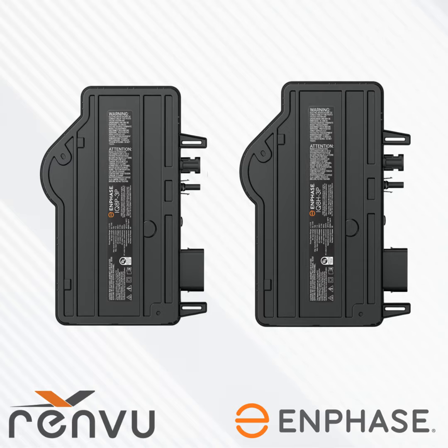So let's look at the specs a little more with a little more focus. We offer two different inverters, the IQ8P and the IQ8H, and the specifications are as follows. The 8P has a max output of 480 VA, and the H has a max output of 384 VA. Most people would just say 480 or 384 watts, but since they're intelligent and reactive power sources that respond to site conditions, technically 480 or 384 VA is more accurate. Whenever I say VA, just think watt. Again, output is 208Y. If your site is a different voltage, add a transformer.